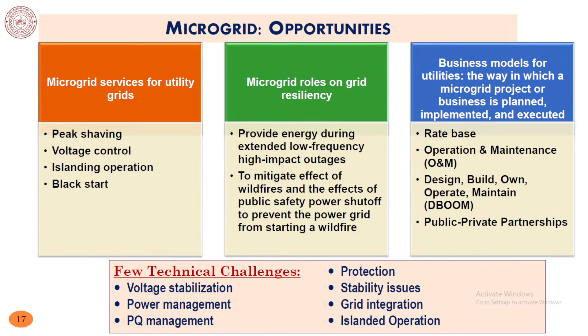Then grid integration and islanded operation, once you have these. Now to achieve these, three levels of control are exercised, at least on the distribution side. One is at converter level, primary control, where we have voltage and current control loops, employing droop control or MPPT control, harmonic and unbalancing controls - this is at converter level. But if you have converter interfaced to a renewable, and then storage, with several renewables forming a microgrid, you need a microgrid energy management system.